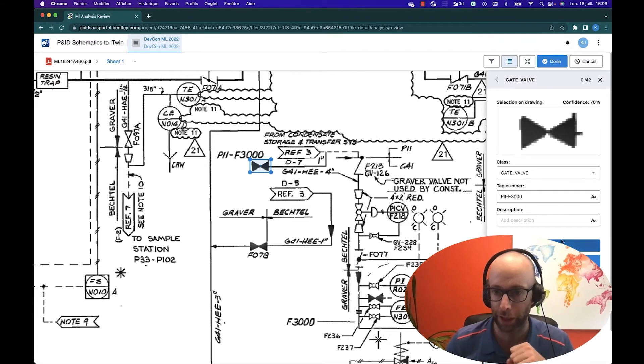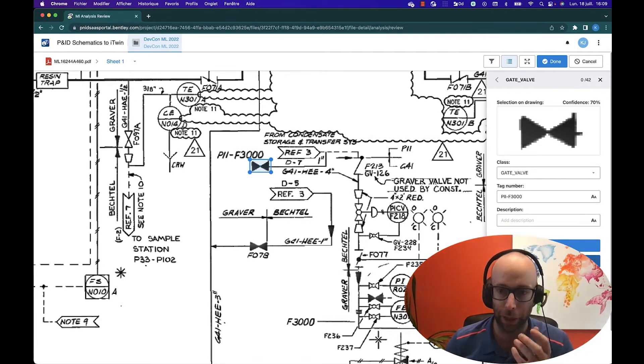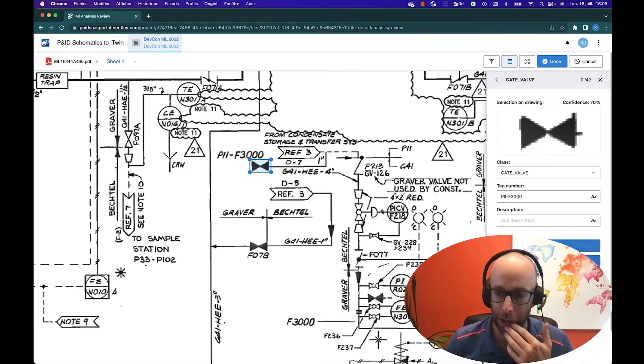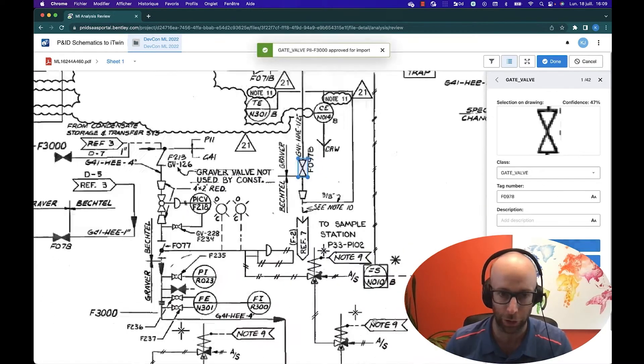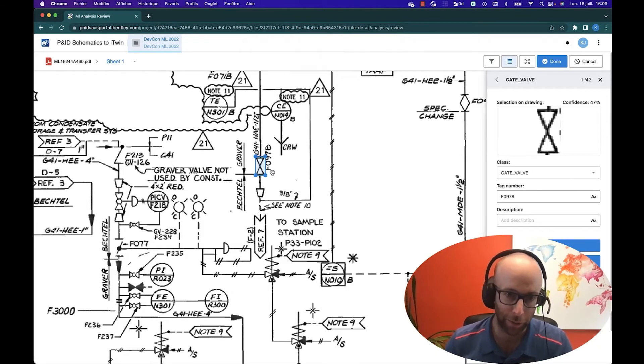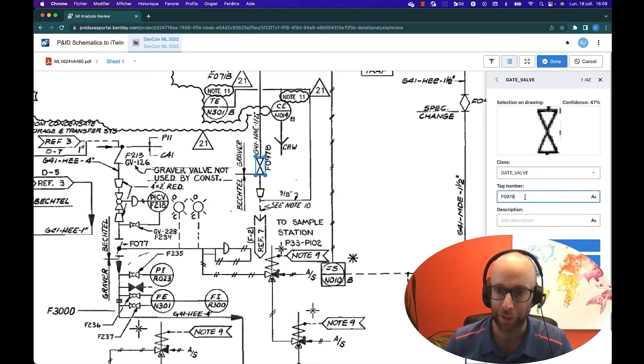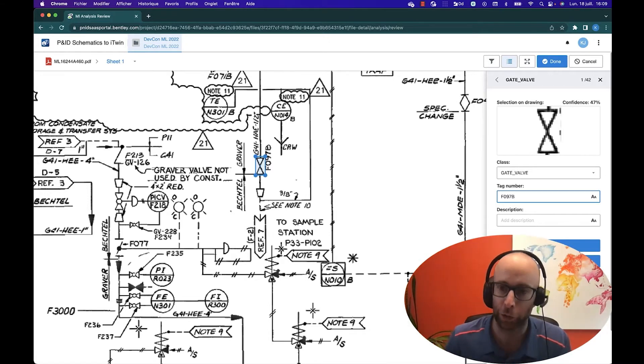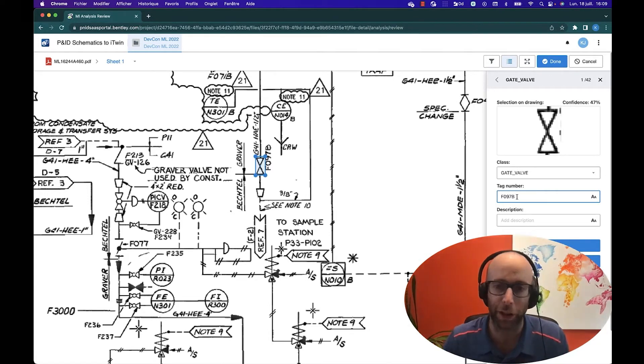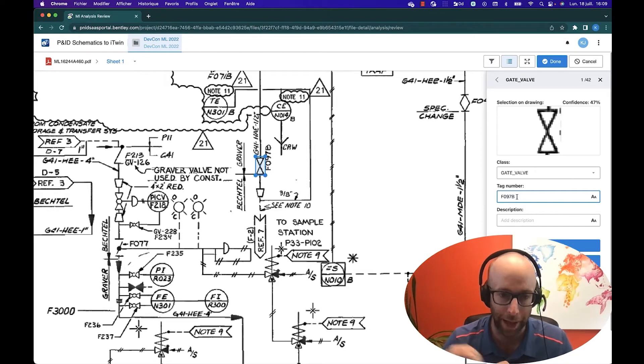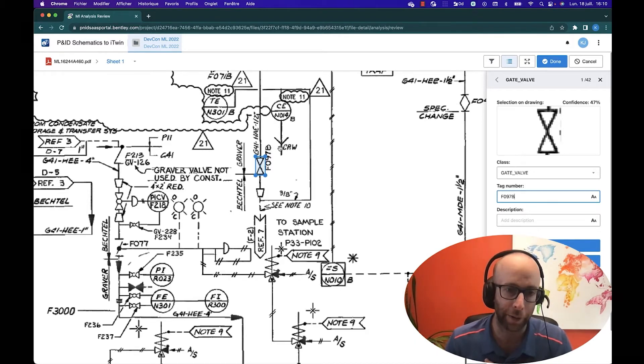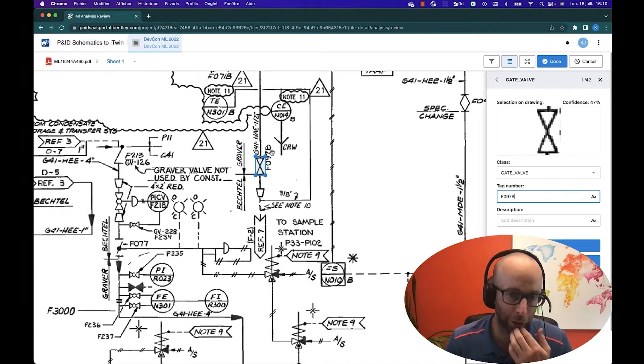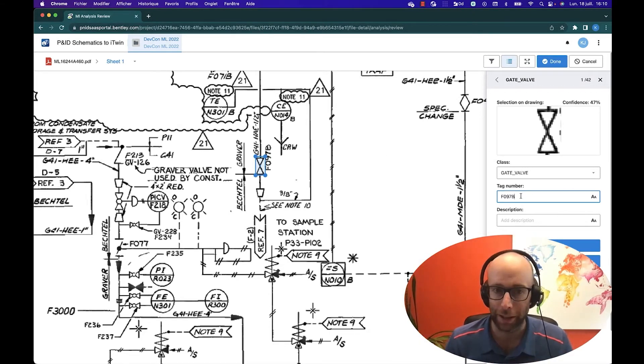We can see here that it was able to grab this tag, recognize the text that was written there, and associate that this tag number was actually belonging to this valve. Every time I review an object, I can either approve it if I think that the machine learning model has done a good job with it, I can ignore it if I'm simply not interested in that class of object, or I can delete it if the model was wrong and shouldn't have detected anything there. Here, everything looks fine. I'll approve it. Here, we have another gate valve. But this time, if we look at the text, it looks like the model was confused instead of an 8. It actually seems more like a B to me. So we can go ahead and correct this and make sure that when we aggregate this data, the user labeled tag will align very well with other sources of information.